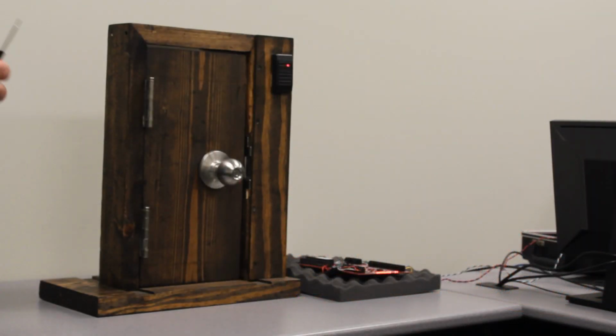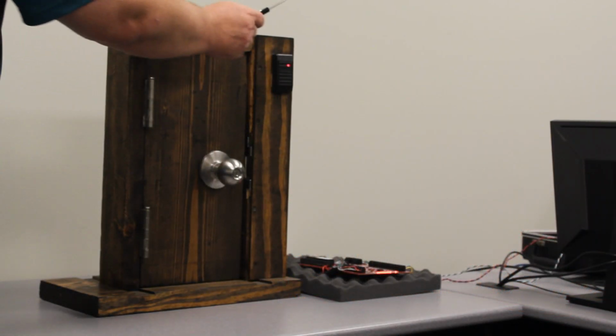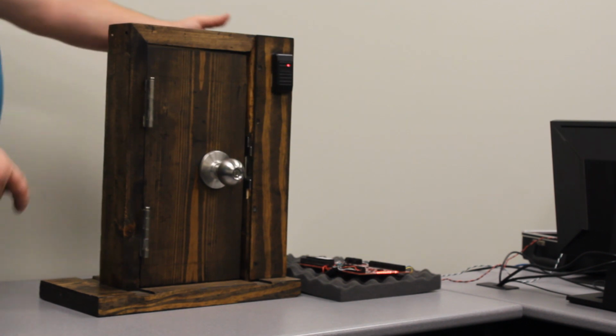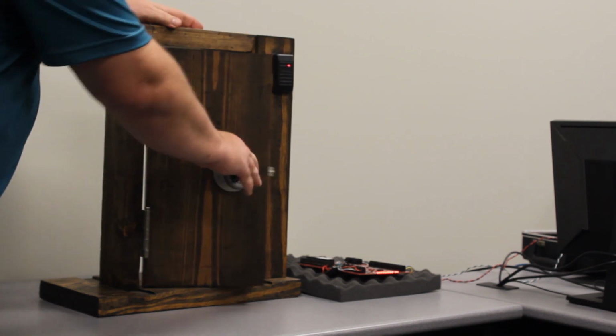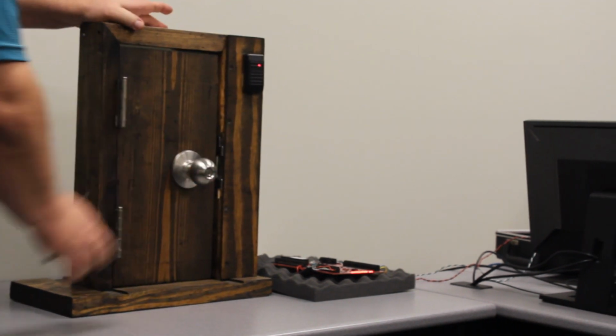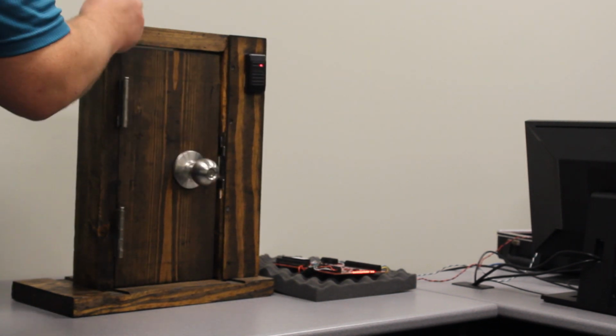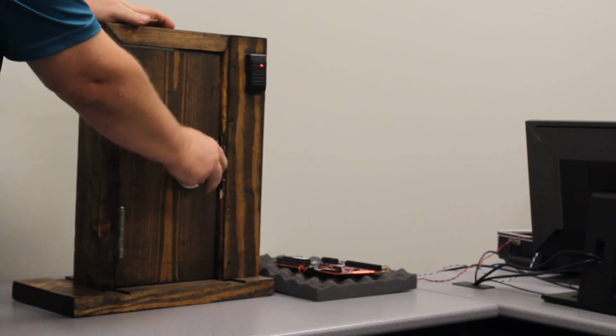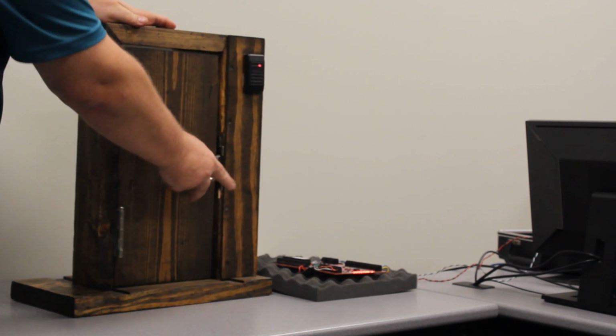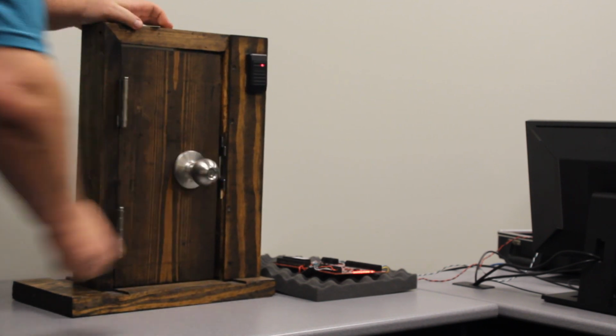And we got everything wired up to the door now. Got 12 volt to the reader. We're gonna push the rex, door relay trips, door opens, resecures, badge the card, access granted, door opens, door resecures, fully functional.